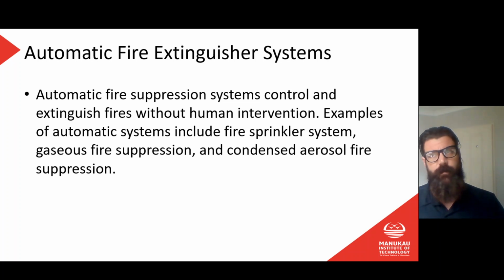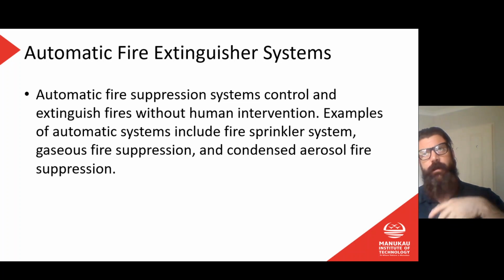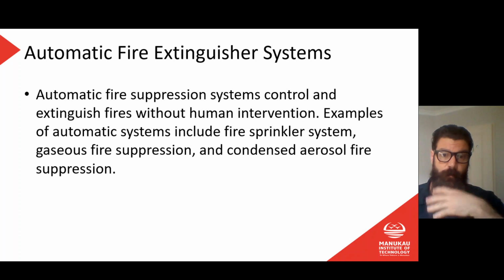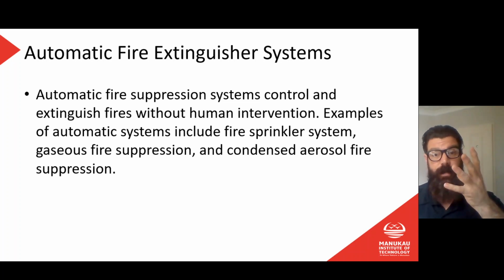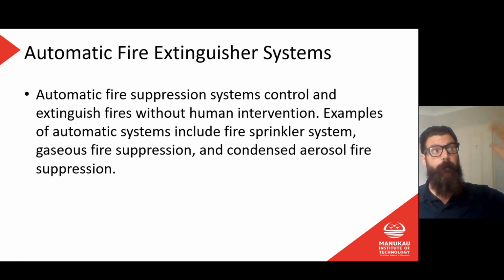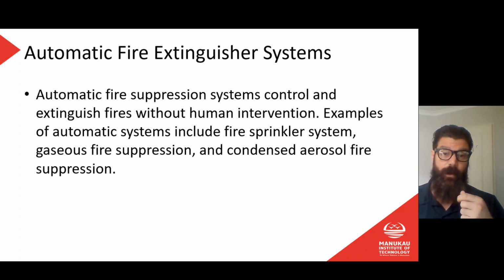Normally you wouldn't put a 57 degree head, for example, in a ceiling space, because ceiling space can get very hot, and we wouldn't want the sprinkler system going off just because it was hot up there and there was no fire. If you think about that, you'll realize that unlike the movies where all the sprinklers go off at once, each individual sprinkler head has its own glass tube and its own valve. So you smash one of them and that one will open. If the fire has spread further, then each of those sprinkler heads will activate individually when they reach the correct temperature. That's really uncommon. A sprinkler system is a very, very effective way of suppressing fires.